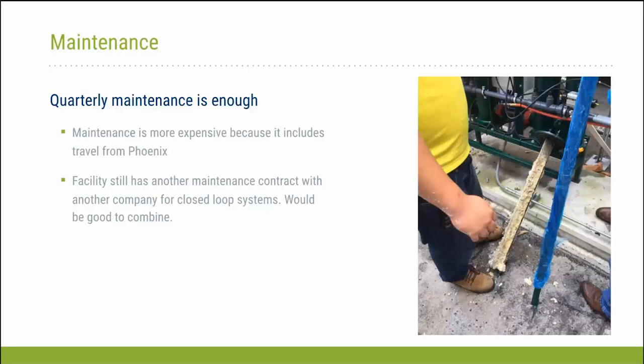Now in our case, now that we have the maintenance contract in place, there is a chemical company that is doing our closed loops. They're taking water measurements of the closed loop, chilled water loop. They're also taking water samples of the open cooling tower loop. The maintenance of this unit is not done, however, through the O&M subcontractor that is doing our water chemistry. Okay, we have a separate contract with the vendor to come out quarterly now and inspect this unit and tweak the settings and also do the cleanings on it.